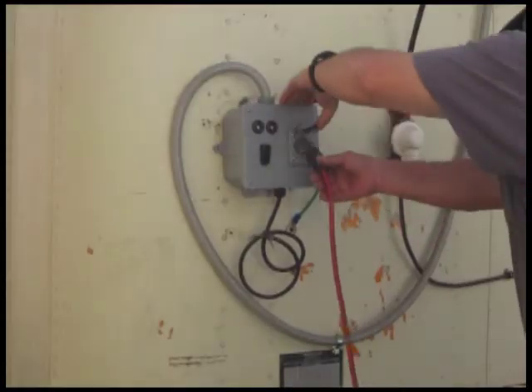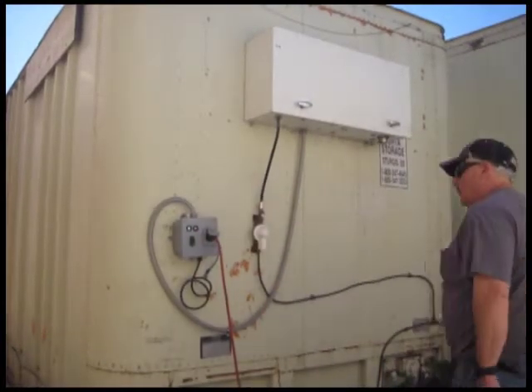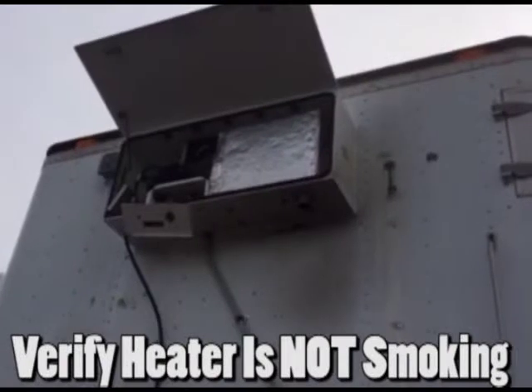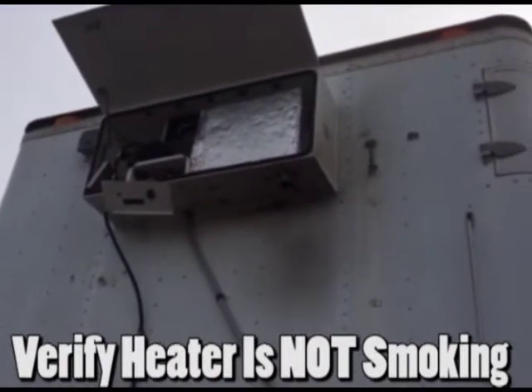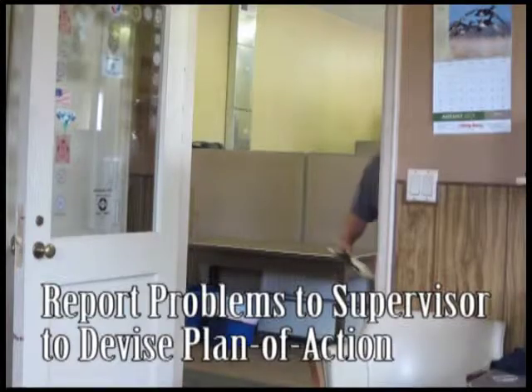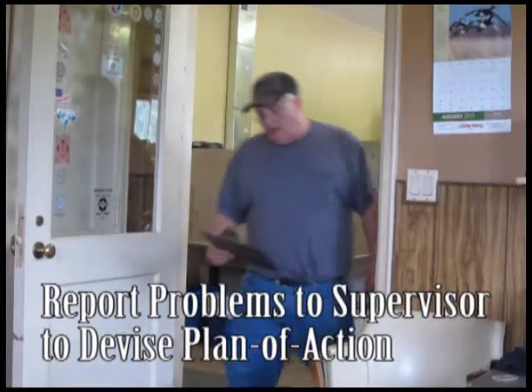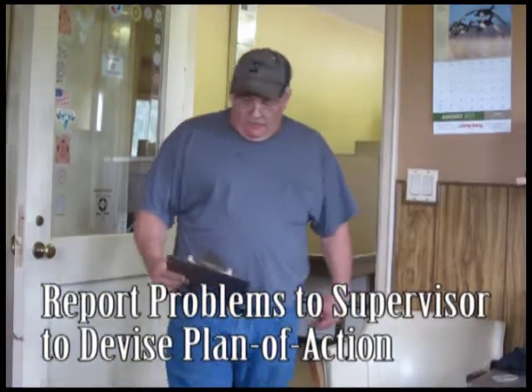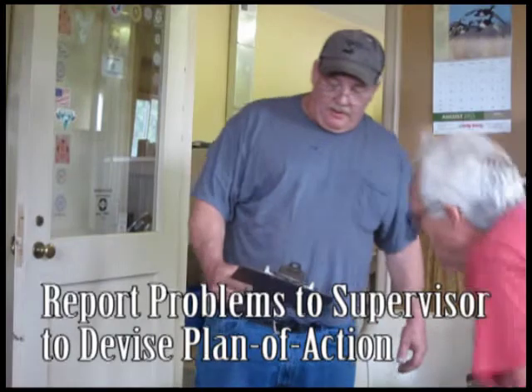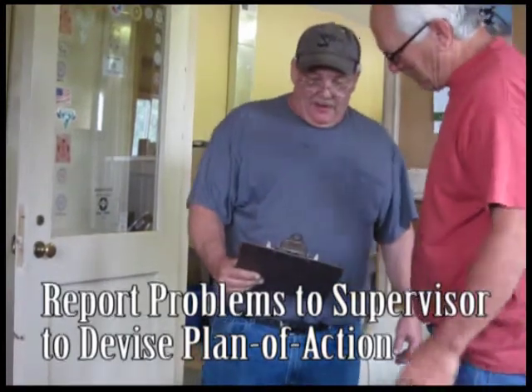Start up and run the heater for 5 to 10 minutes to check that all components are in working order. Check to ensure heater is not smoking or producing soot. Report any issues found during annual preventive maintenance with the supervisor and devise a plan in order to correct any operational issues before approving the heater for usage.